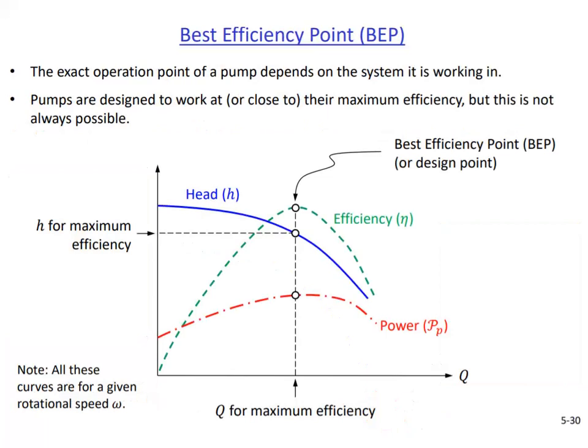Best efficiency point is the point with the maximum efficiency. It is desired to operate the pump close to this point, which may not always be possible. As we said earlier, the system in which the pump is used determines where it operates. If the system is not suitable for our pump, in other words, if we did not select the proper pump for our system, or maybe if the system characteristic is not constant but changing with some factors that we cannot control, the pump may work at a point far away from its design point.